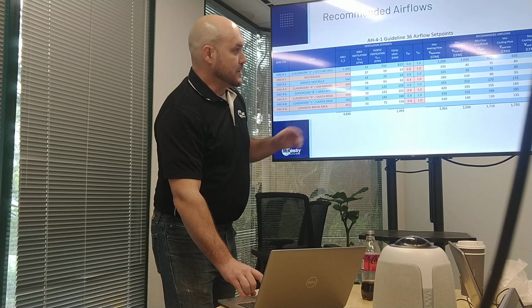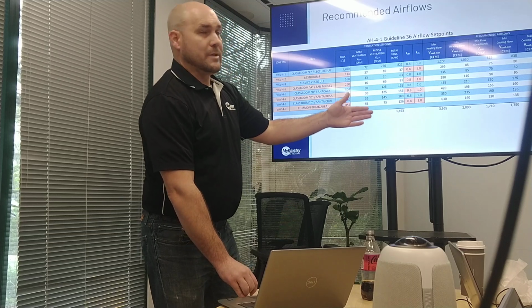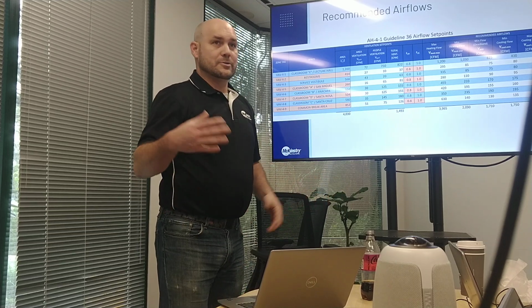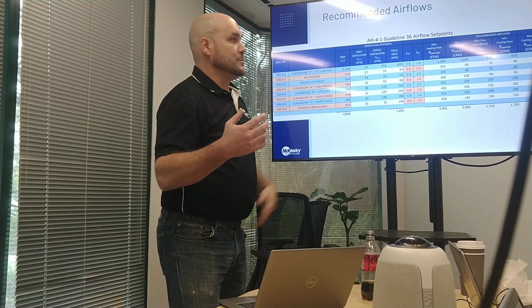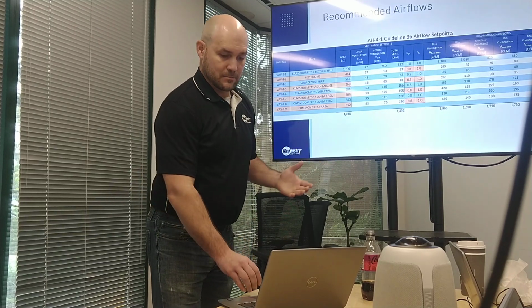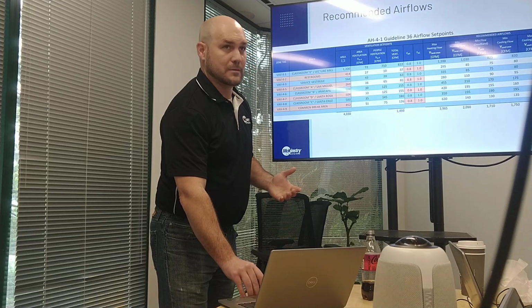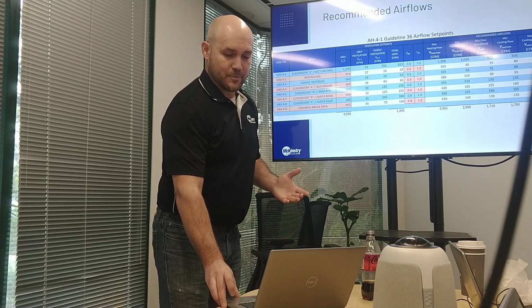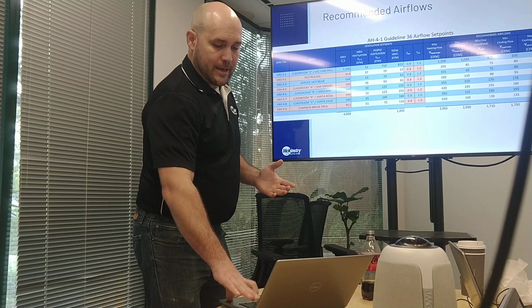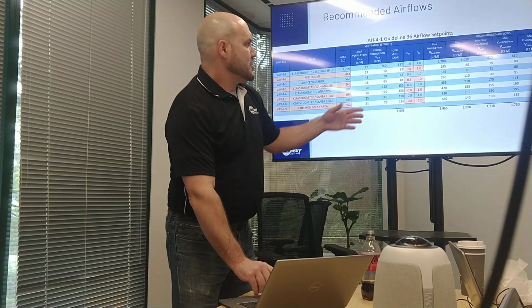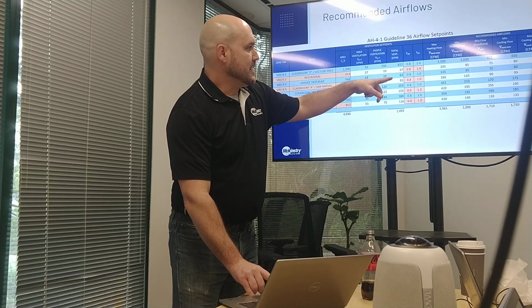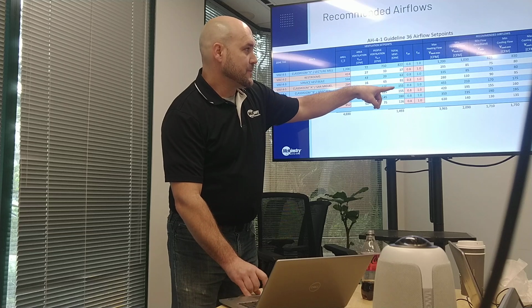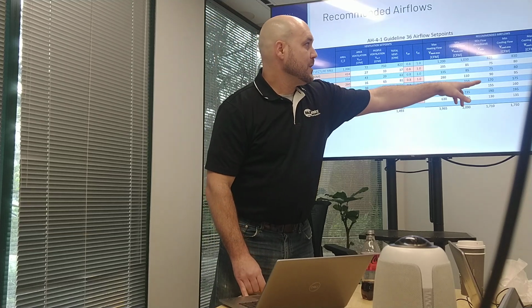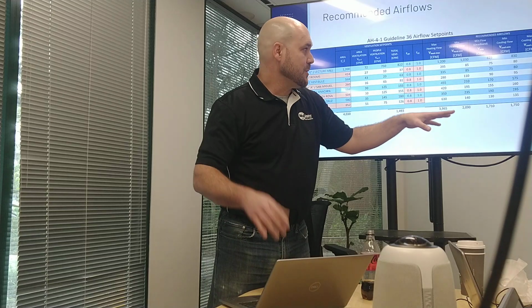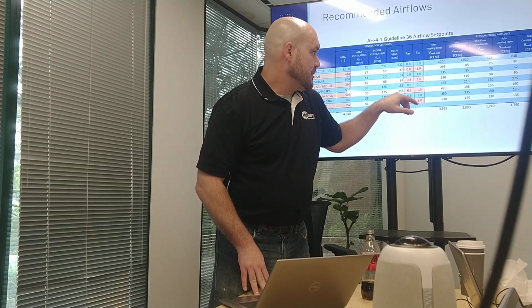So yeah, this is ultimately the output. It's just, hey, controls contractor, as you're reprogramming logic, plug these values in instead of what was there. So obviously a little more thoughtful. There's some analysis and engineering that went into it. But what might jump out at you is the ventilation CFM for this, like, hey, 155. All right, that minimum is 170. So there's a little bit of a factor. Just rounding up slightly. 155.